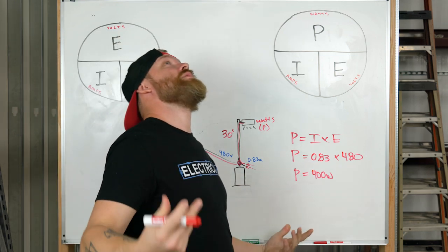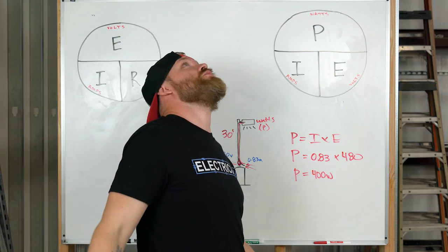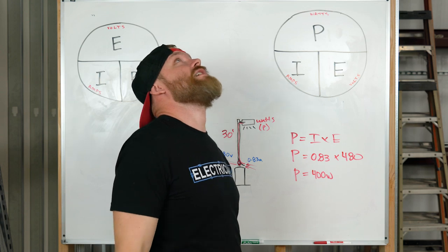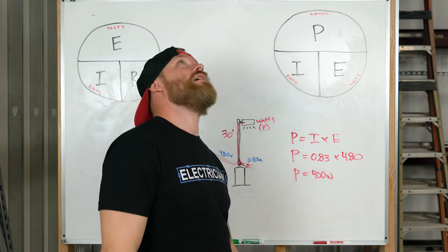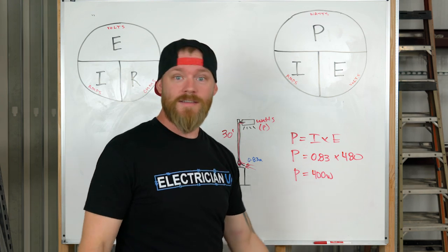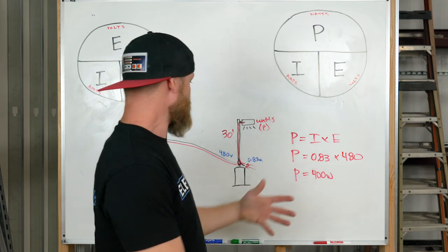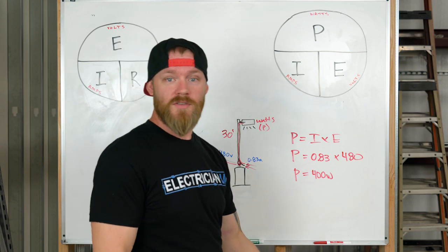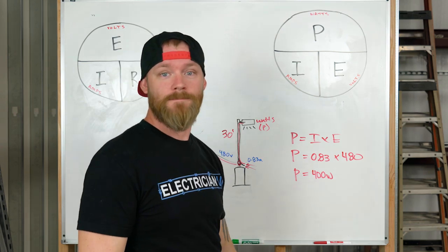We can look up, be like, oh, it's the skinny tube with the skinny lamp. So that's definitely high pressure sodium. And from our calculation, we can figure it's 400 watts, not 1,000 or not a 600 watt. But that's just a good useful thing to be able to figure something out if you're in a pinch on the job site.